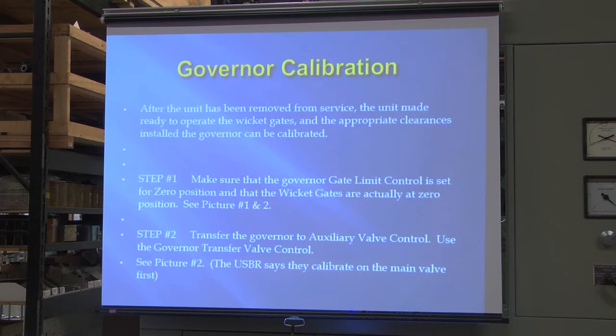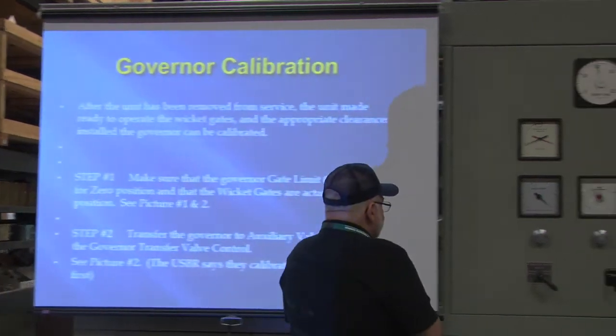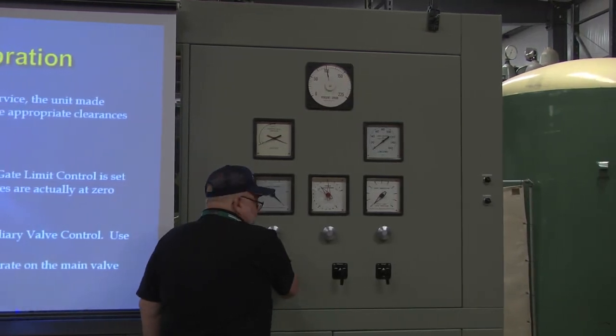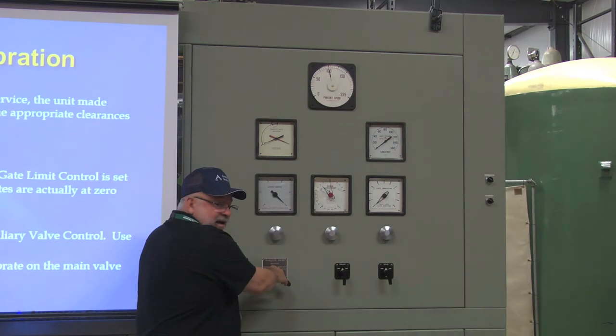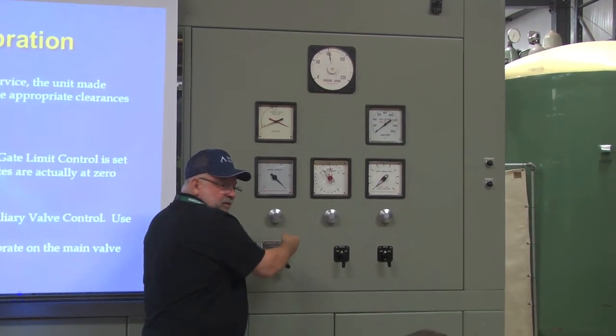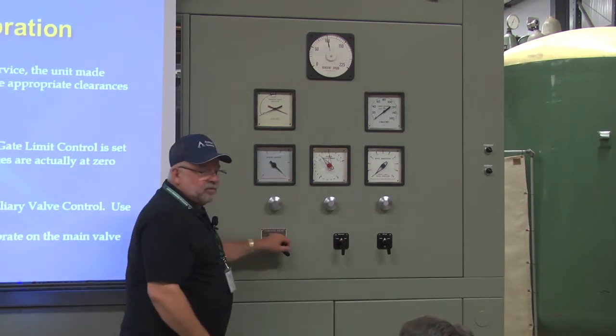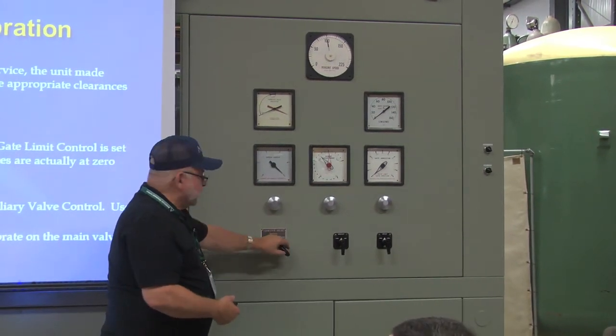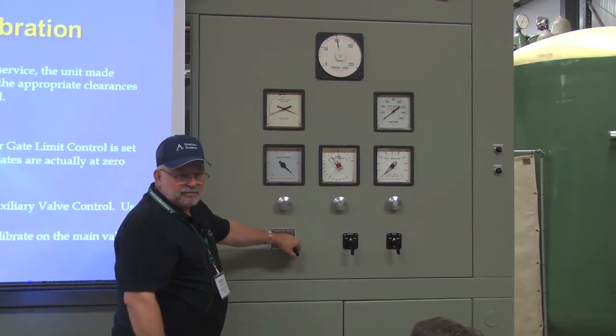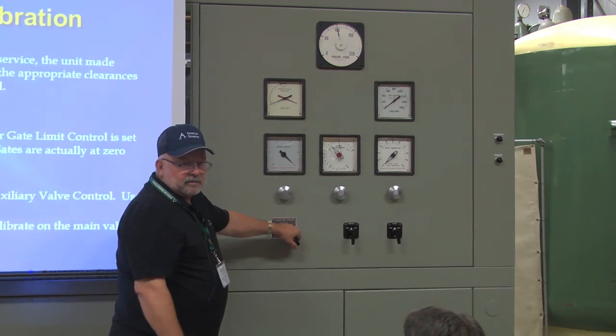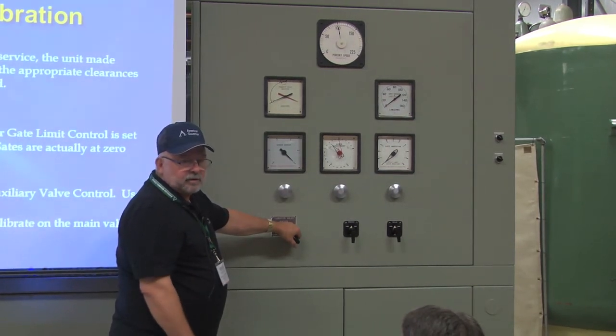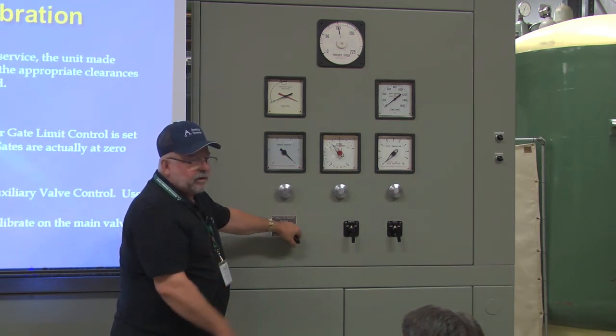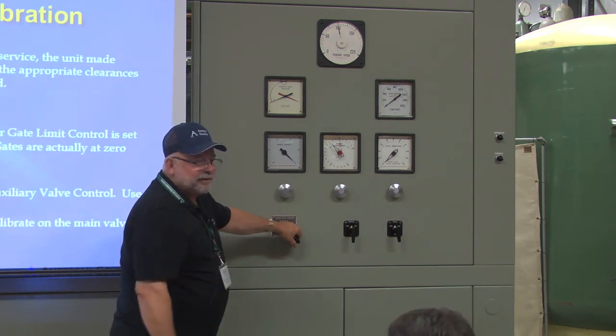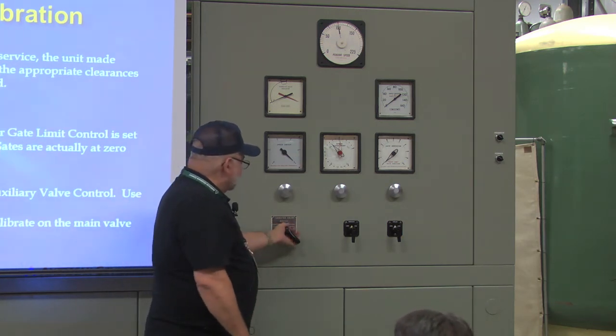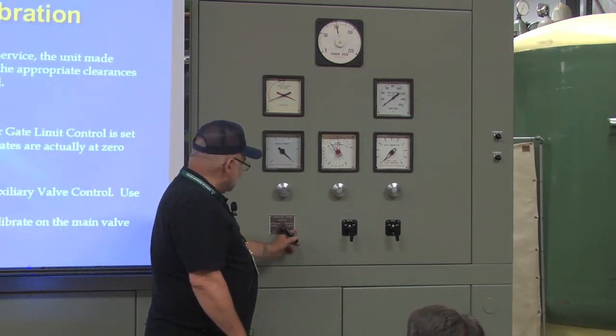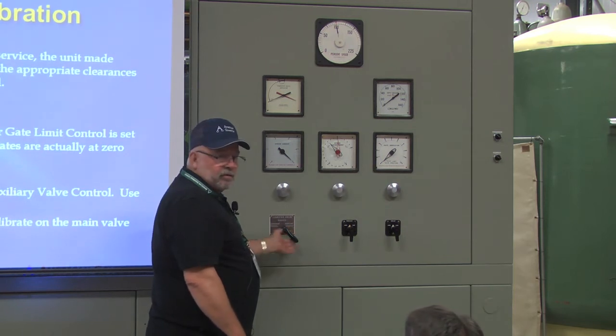Transfer to the auxiliary valve using the governor transfer valve control. That's here. You'll notice almost all the Peltons are different than the Woodwards. You have to pull out, go to the position, and go in. I had a situation where I was doing testing on a unit with brand new operators. He'd come from a Woodward governor place. I said, prepare that thing, get it ready for the governor. I want to warm it up, so go ahead and put it in governor control. It was about 8 o'clock at night, and we were going to go in and eat a steak they brought from the cookhouse. I said, we'll warm this thing up. Well, he pulled it out and went from auxiliary valve control to governor control, but didn't push it back in.